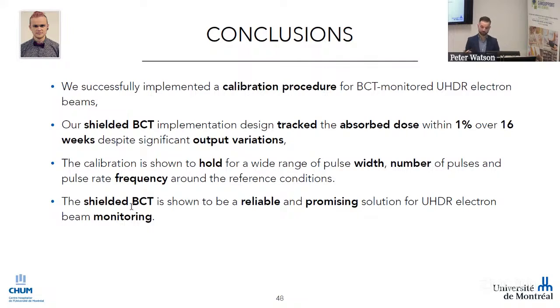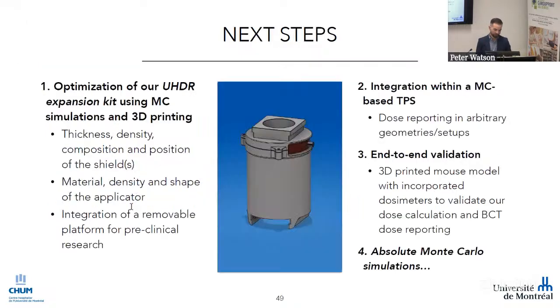The calibration was shown to hold for a wide range of pulse width, number of pulses, and pulse rate frequency. And considering all this, we conclude that the shielded BCT is a quite reliable and promising solution to monitor the dose we deliver with our FLASH beam. So that wraps up the work we've done in our group.